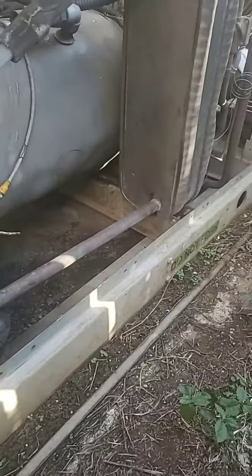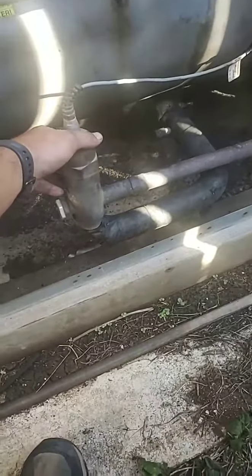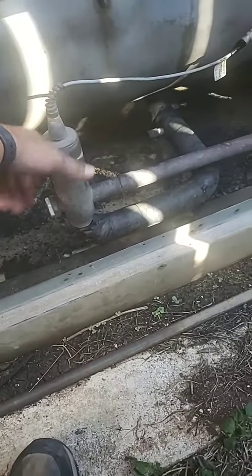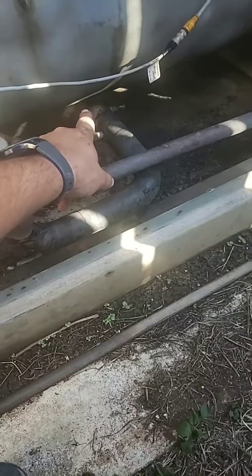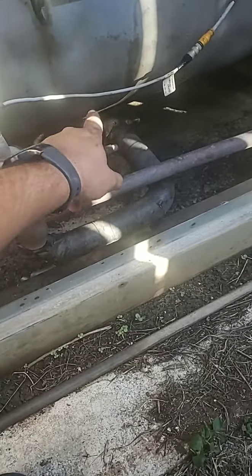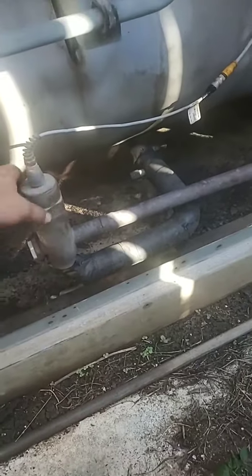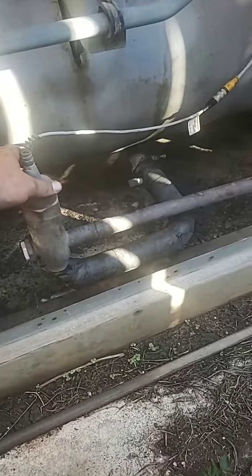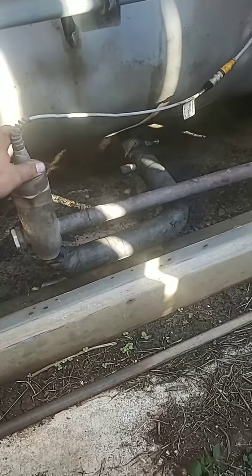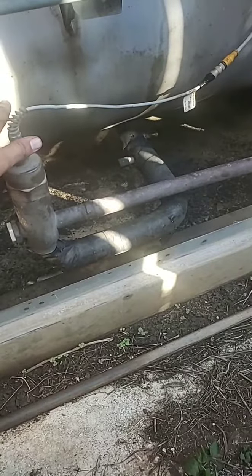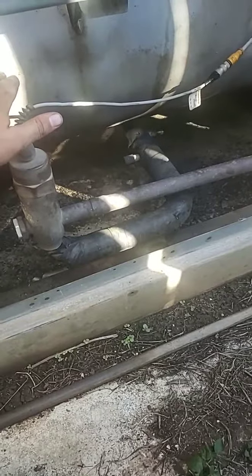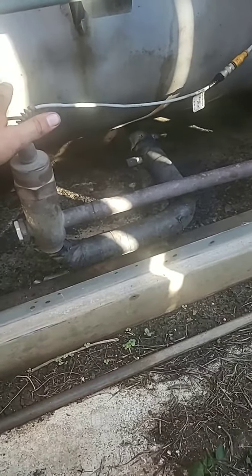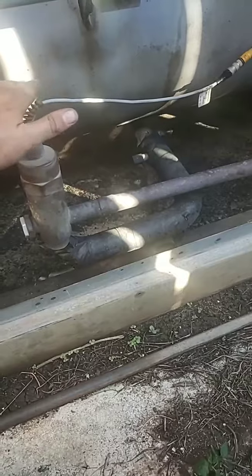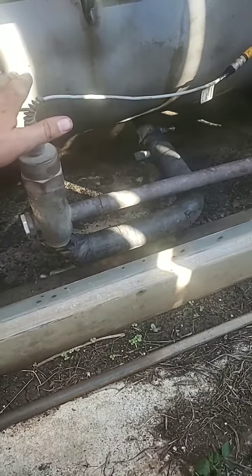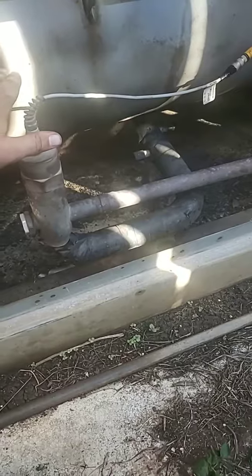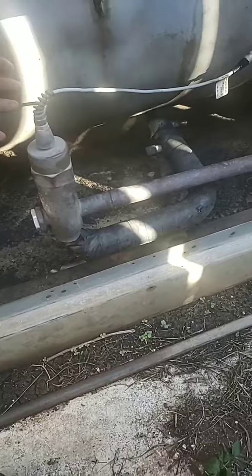So this is where we come out of the economizer and hit our EXV. This EXV then obviously dumps into the bottom of the evaporator barrel. Keep in mind, chillers like this run a flooded evaporator, which means that the evaporator actually has liquid all the way up above the water tubes that are running through it inside. So you're going to constantly maintain a solid level of liquid inside of this evaporator, and that's what it's supposed to do. Hence the term flooded evaporator.